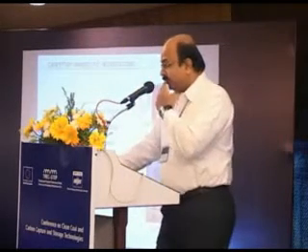In this unit, we didn't have so much, but why we do that modification is, if you can see the bottom portion, you can see some black lines there. Upgrade means you are upgrading material? No, sir. Actually, we didn't do any material upgrade. We have maintained the same material. Maybe a certain portion. What is the spacing of the tubes? Each tube is held by a spacer.